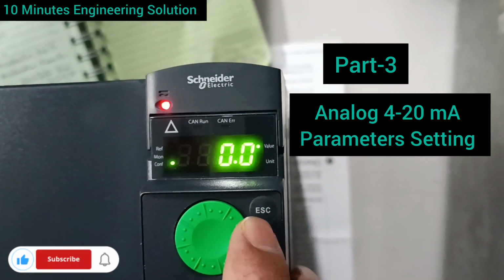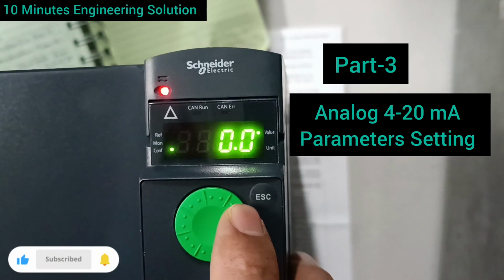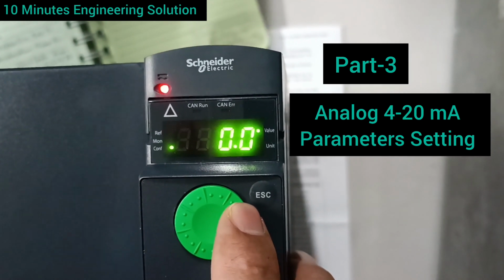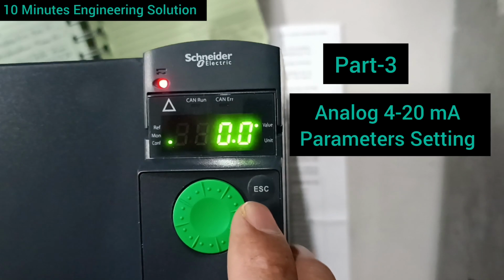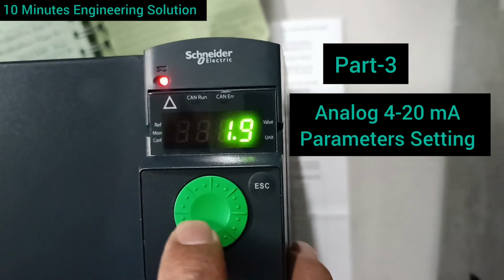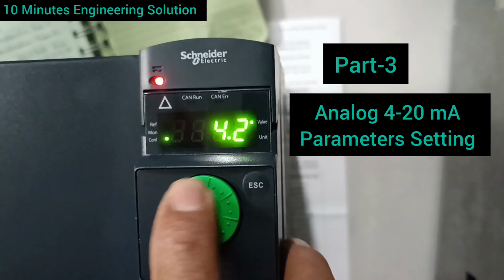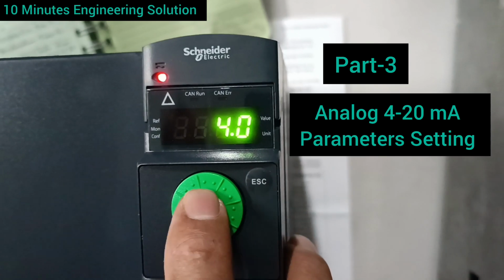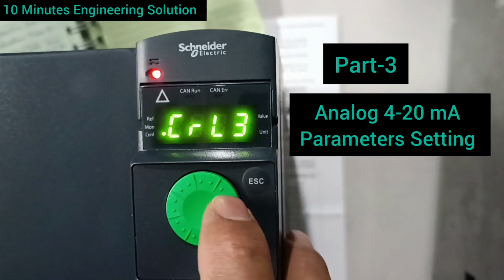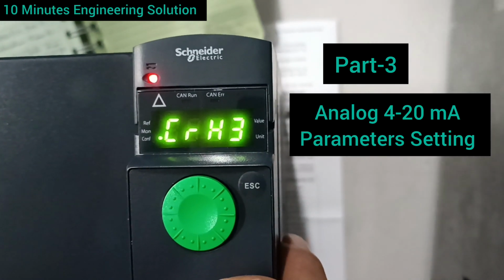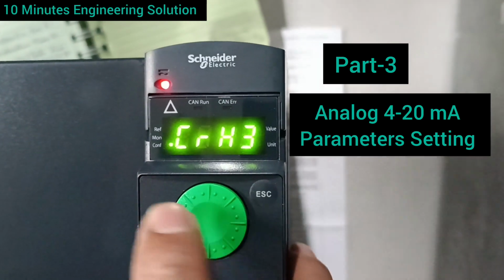The default setting is 0, but I need to set 4 to 20 milliampere. The minimum value will be 4 milliamps, so I'll increase the data to 4.0. This is the analog input CRL3, and the next is CRH3, which means the maximum current setting.